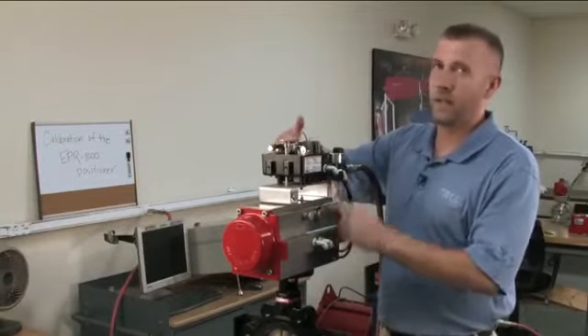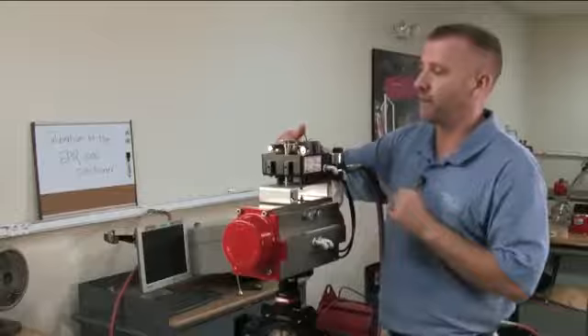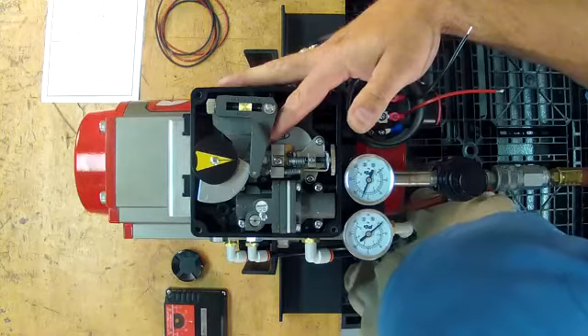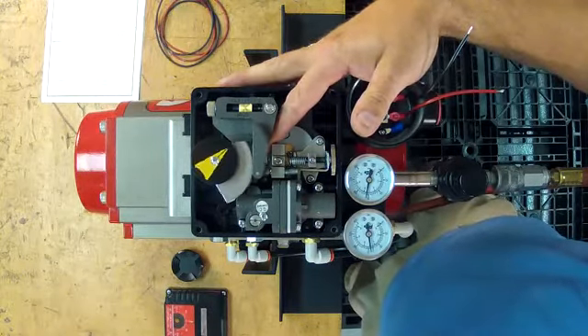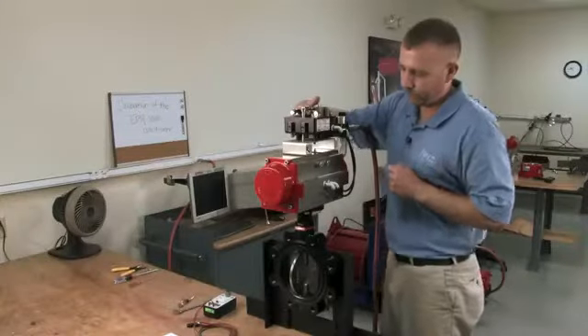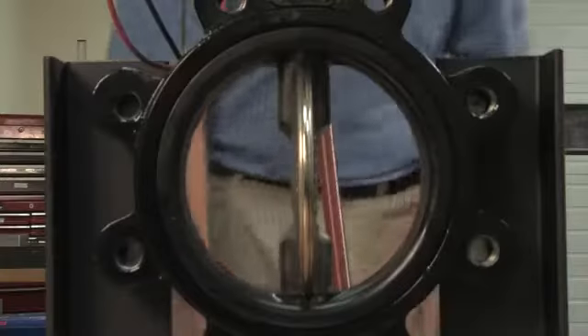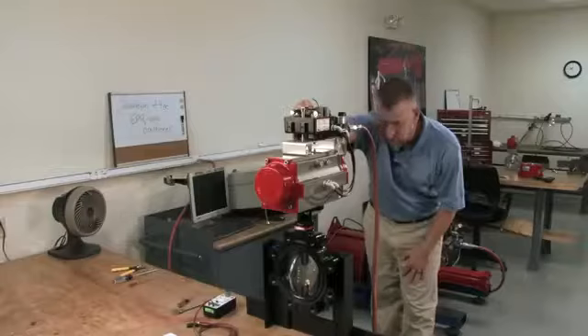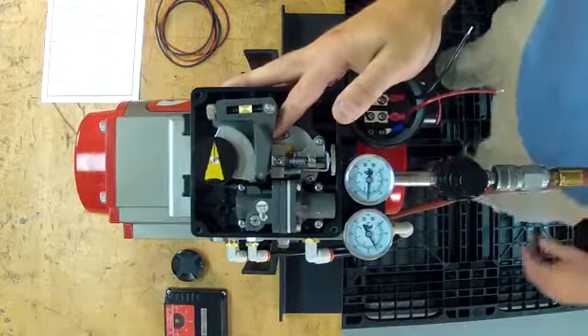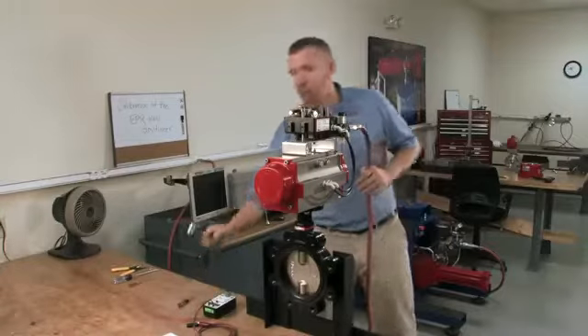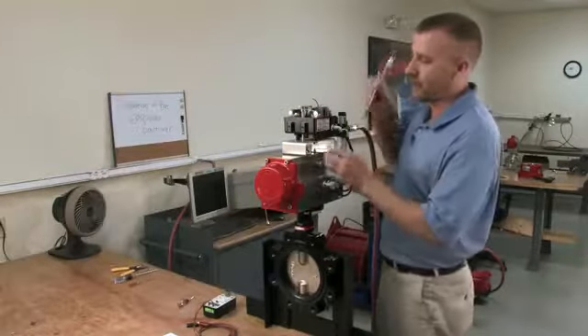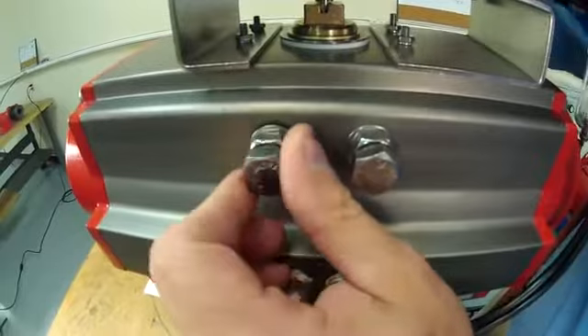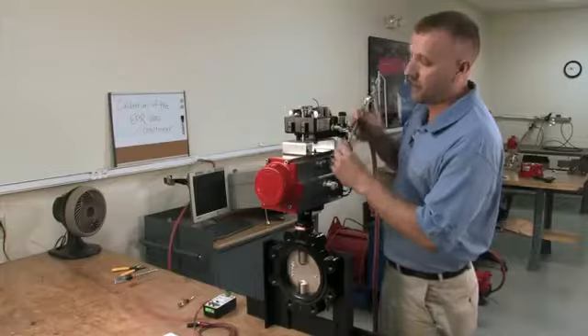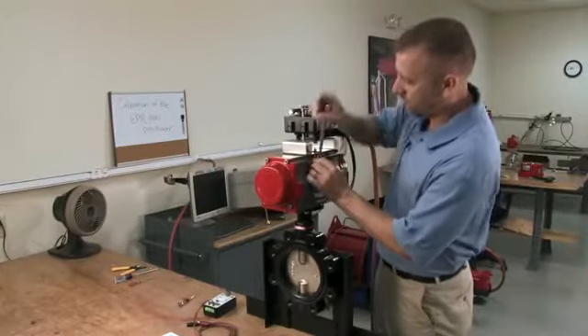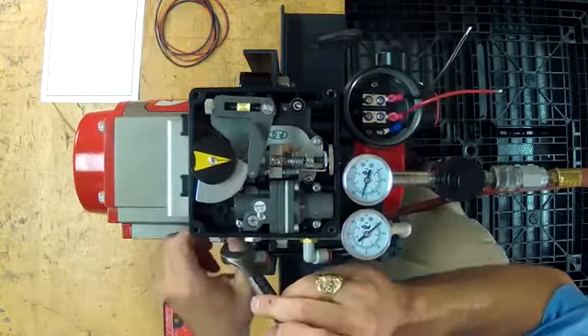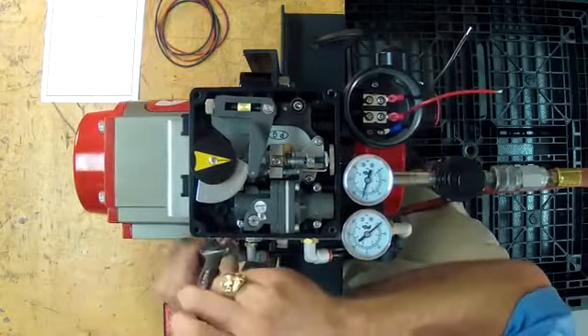So we're going to run this thing counterclockwise by pulling on our counterweight, kind of manually. And you want a nice parallel disc here with straight through flow, which that looks fine. But I'm going to demonstrate how to adjust that. Before adjusting your travel stops, you must relieve the spring force that is on your travel stops. This being our open stop, you have 5 degrees positive and 5 degrees negative travel on the open and closed stop.